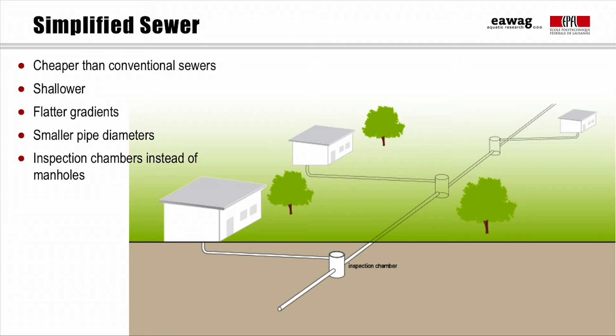Wherever possible, simplified sewer systems should be preferred, as they are 20 to 50% less expensive than conventional sewers and much easier to implement. The simplified sewer describes a sewage network that is constructed using smaller diameter pipes, laid at a shallower depth and at a flatter gradient than conventional sewers. Simplified sewers can be installed where there are no heavy traffic loads, for example within a condominium, in narrow alleys, or underneath sidewalks, allowing for more flexible design at lower costs.